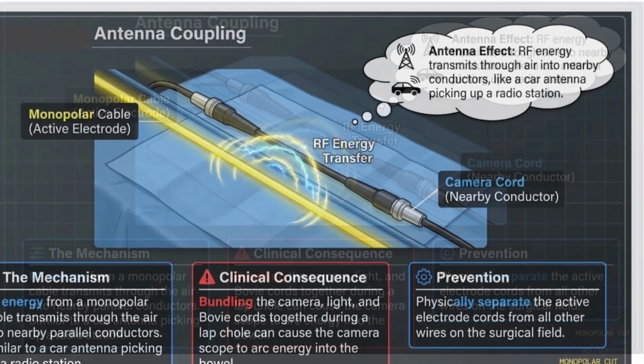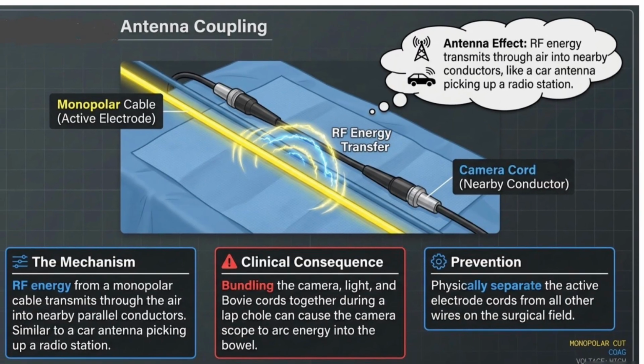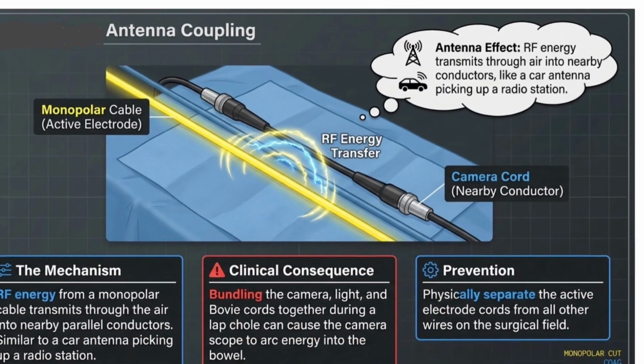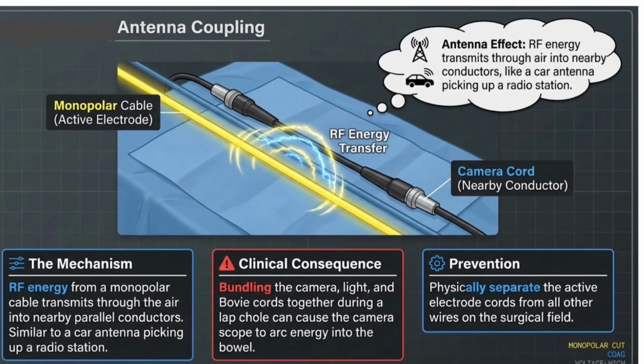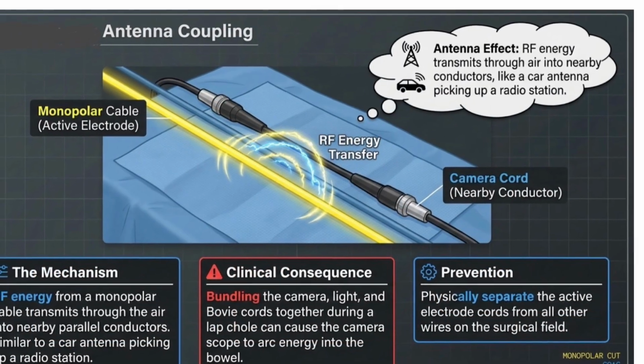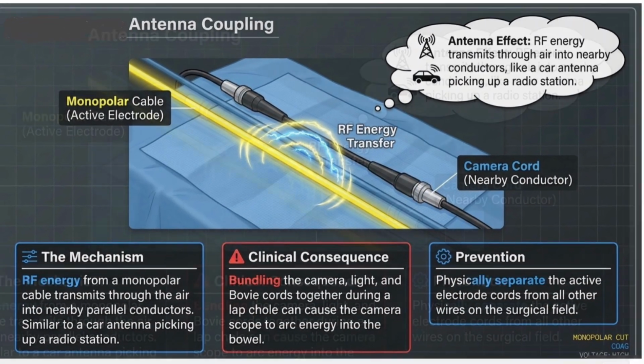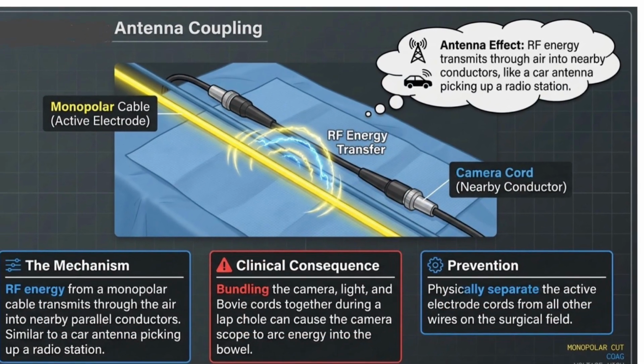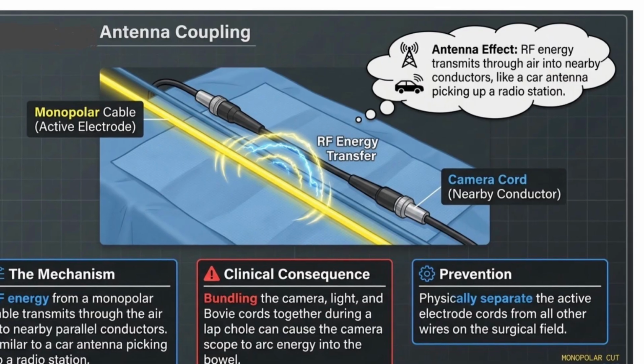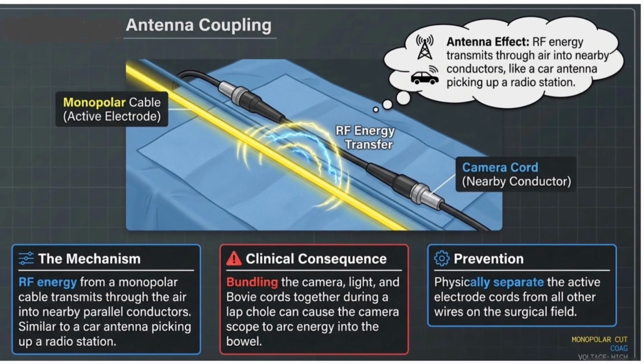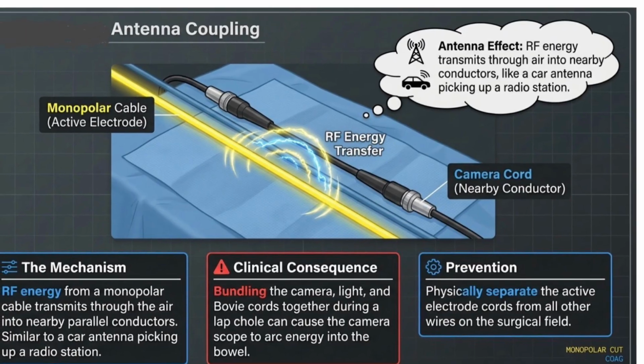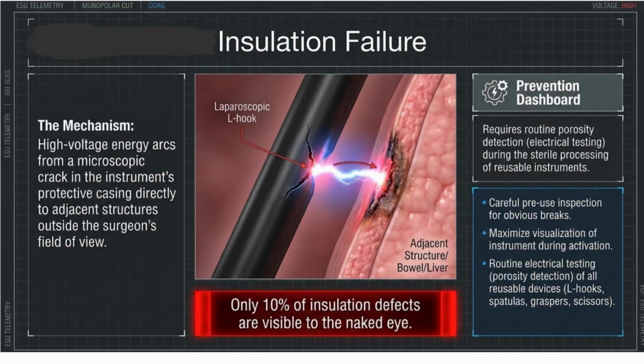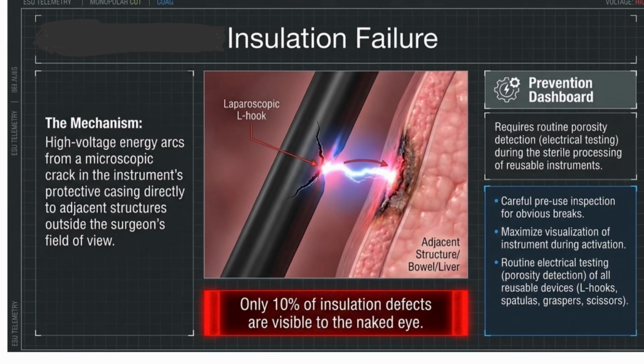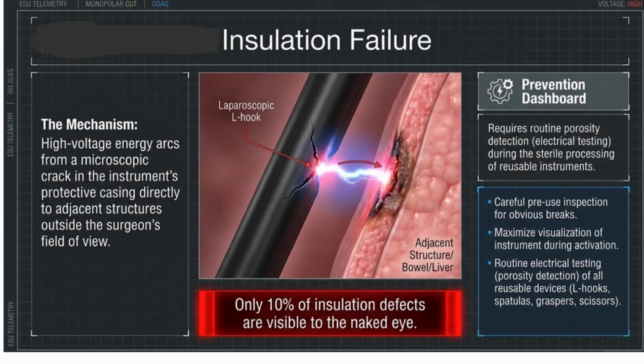Antenna coupling, the antenna effect: the radiofrequency energy transmits through air into nearby conductors, like an antenna picking up a radio station. So the monopolar cable, the active electrode, passes radiofrequency energy to the nearby camera cord. Bundling the camera, light and bovie cords together during a laparoscopic cholecystectomy can cause the camera scope to arc energy into the bowel. This is prevented by separating the active electrode cords from all other wires of the surgical field. Insulation failure, the mechanism: high voltage energy arcs from a microscopic crack in the instrument's protective casing directly to adjacent structures outside the surgeon's field of view.